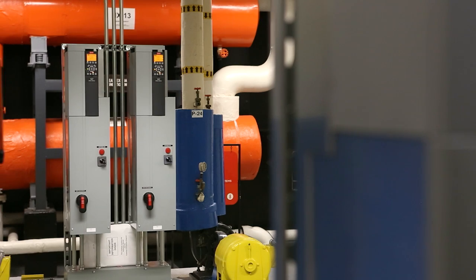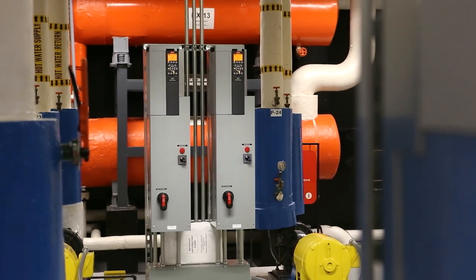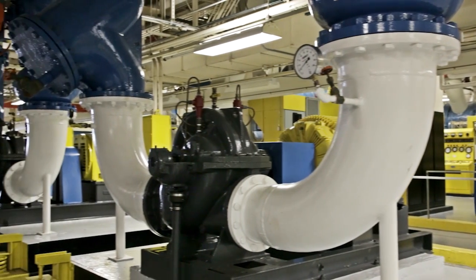We're pumping water from mechanical floors on 64, 63, 34, third floor, and down the concourse, all over the entire building. It uses a tremendous amount of energy. In 2000, Winthrop began its first variable frequency drive retrofit project, addressing the pump motors responsible for the domestic water supply. At the time, the building's four water pumps were still being controlled by the original two-step drives, which were difficult to maintain.